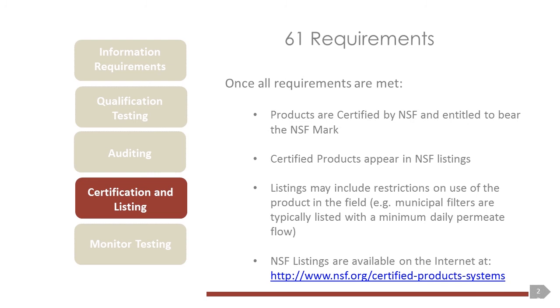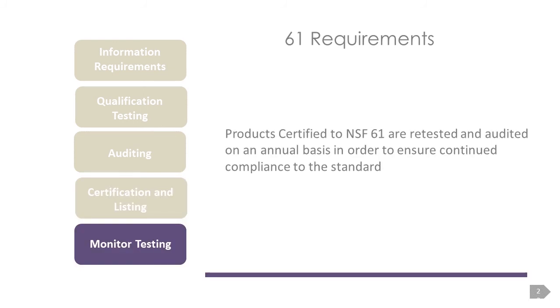Once all requirements are met — once the product has successfully passed qualification testing and the audit has been successfully completed — products are certified by NSF and entitled to bear the NSF mark. Certified products are then put into NSF public listings. For these municipal filters, the listings typically include restrictions on the use of the product in the field, such as a minimum daily permeate flow rate, because those numbers were used to evaluate the actual product as tested. NSF listings are made publicly available on the internet through NSF's webpage. Products certified to NSF 61 at NSF International are retested annually as well as audited annually to ensure the product continues to comply with the standard.